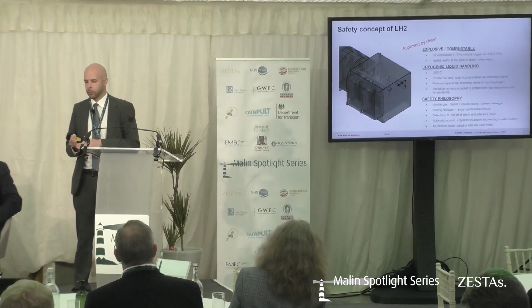So the safety philosophy is that this is a volatile gas. We need to avoid exposure, so we work with this double wall piping. All of the hydrogen can be detected and set off an alarm, so we can have an emergency shutdown in a safe manner to avoid any leakages, and all of the leakages will be routed to the safe area, and the only safe area on board the ship is the vent mast.